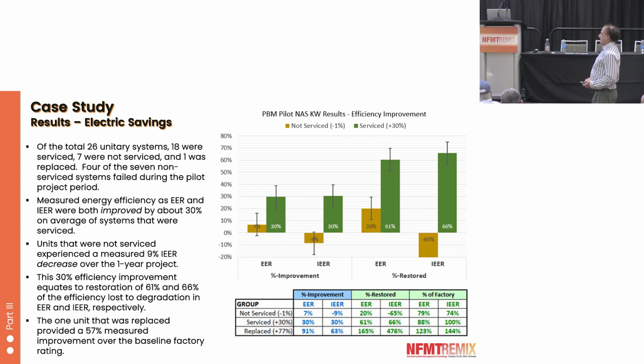The units that were not serviced over the year actually had a decrease in efficiency of 9% that we measured. The 30% improvement equates to a restoration of about 2/3 of what was lost. So if we took the factory rating of the unit and measured what it was actually operating at in the field several years later, we were able to recover 2/3 of that loss with this program.